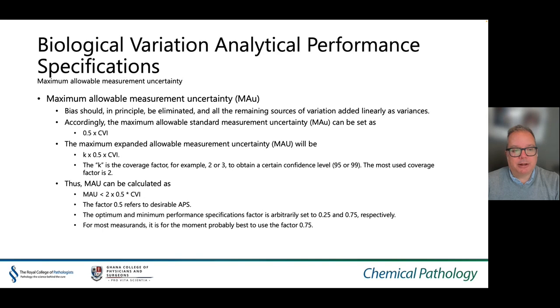The most commonly used coverage factor is 2. Thus, maximum allowable measurement uncertainty can be calculated as less than 2 times 0.5 multiplied by CVI. The factor 0.5 refers to the desired specification, and the optimum and minimal performance specifications are arbitrarily set at 0.25 and 0.75 respectively. For most measurements, it is probably best to use the factor 0.75.